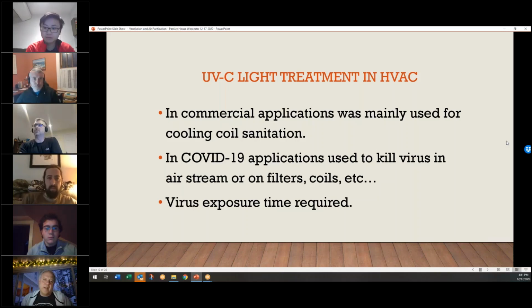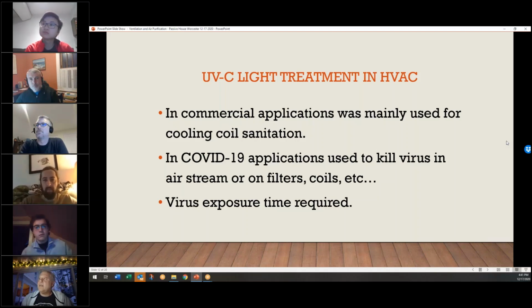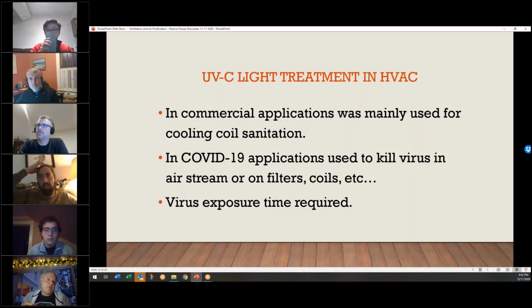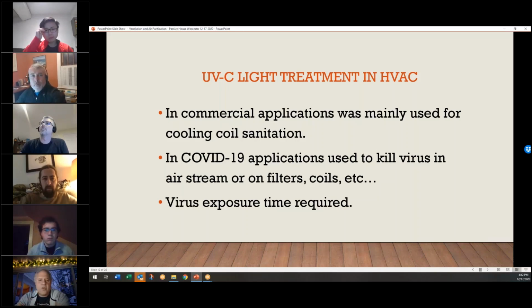So that's one of the considerations of using UVC light. It's definitely something you want to use, but a lot of the applications where you see it used are in portable air cleaners, and they show the UVC light in there. And in these, if the virus gets captured by the HEPA filter or the filters in the unit, the UVC light will then kill it immediately. It won't have to wait and die after a few days. It's going to die after continued exposure to the light. So that's a very common thing now, UVC light we've been seeing employed. And if you go to the next slide, I think it just shows a picture of a.